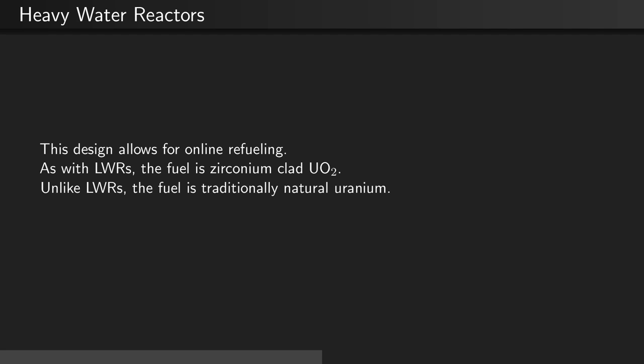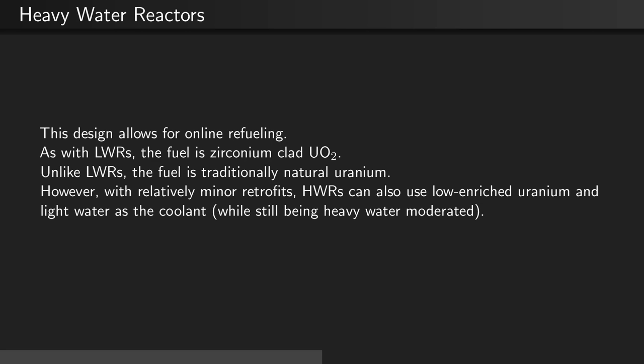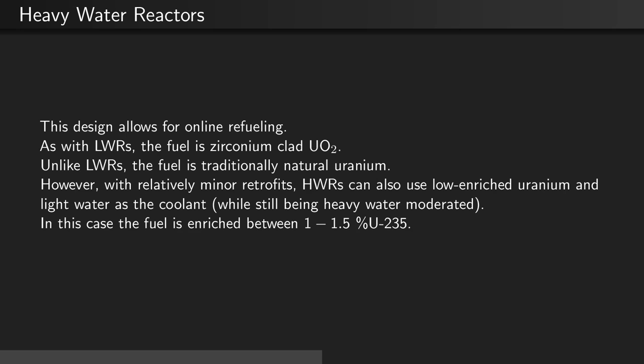As with light water reactors, the fuel is zirconium-clad uranium dioxide. Unlike LWRs, the fuel is traditionally natural uranium. However, with relatively minor retrofits, heavy water reactors can also use low enriched uranium and light water as the coolant, while still being moderated by heavy water. In this case, the fuel is enriched to between 1 and 1.5% U-235.